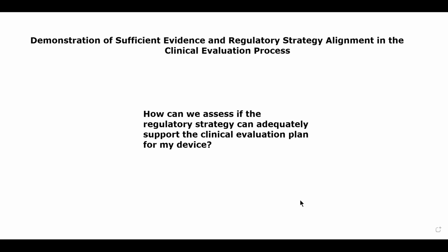Where does my device fall in the therapeutic landscape? How does my device compare to other options, other therapeutic options, alternative options, comparative options? Where do you fall? And what is a regulatory agency or authority or even a notified body looking for from you? What are they looking for in your regulatory strategy? So I like to start at the end and say my final goal here is to have a convincing and justified CER that verifies that this device meets the general safety and performance requirements.